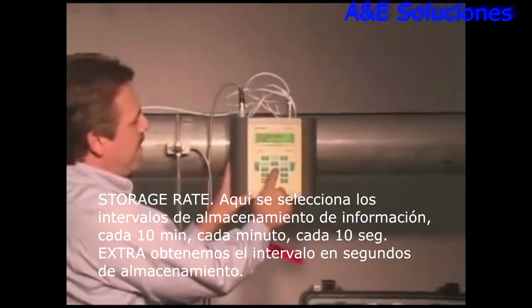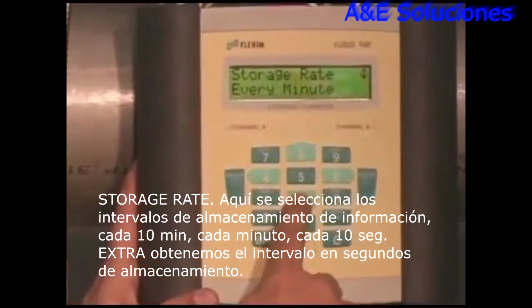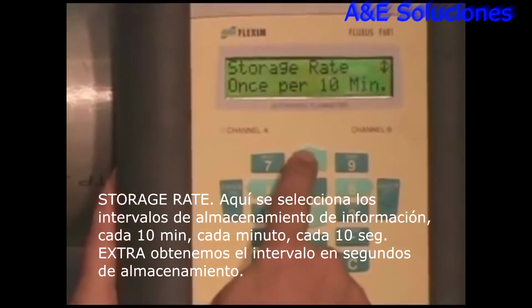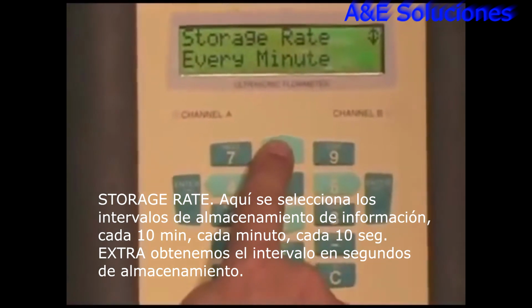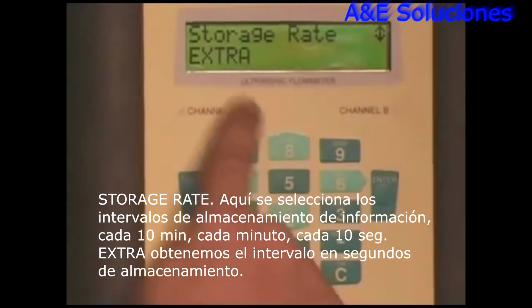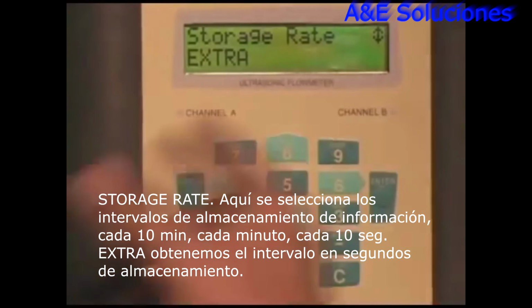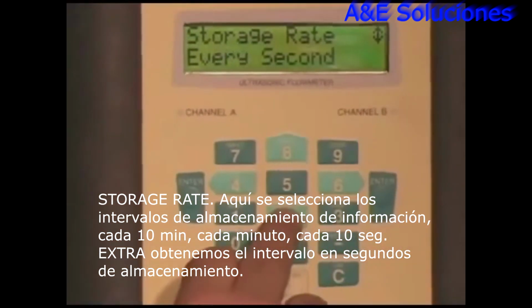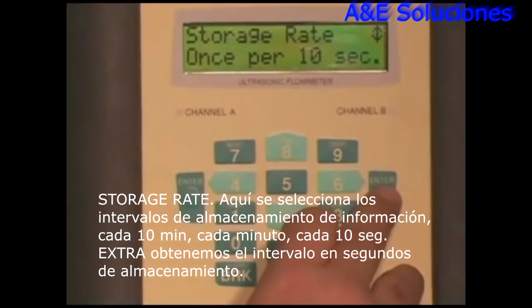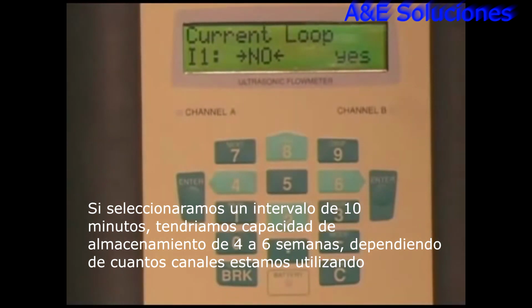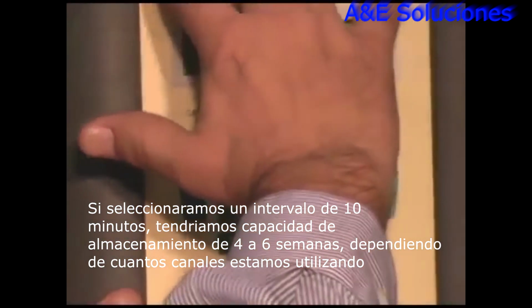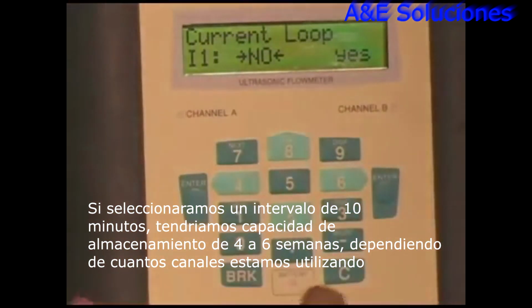Storage rate, here we can choose what interval rate we want to store data at. Every 10 minutes, every minute, every 10 seconds. We could choose extra, in which case we could define the number of seconds we want to store data at. Let's say I choose 10 seconds. Now, if I choose a storage rate of about 10 minutes, the meter will store from 4 to 6 weeks worth of data. It depends on how many channels we're operating. If we're operating 2 channels, it essentially will cut the time down in half.